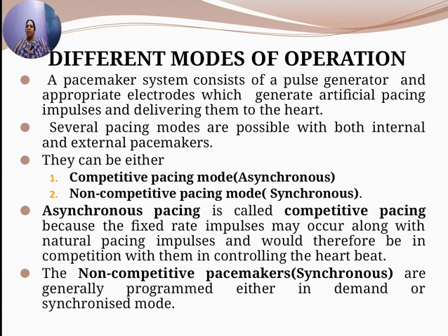Whereas the non-competitive method uses pulse generators that are either ventricular programmed or atrial programmed. The ventricular programmed pacemakers are designed to operate either in the demand mode, that is R wave inhibited, or the standby mode, R wave triggered, whereas atrial programmed pacemakers always work in synchronized mode with the P wave of the ECG. So these are the two types of pacing modes, competitive and non-competitive.